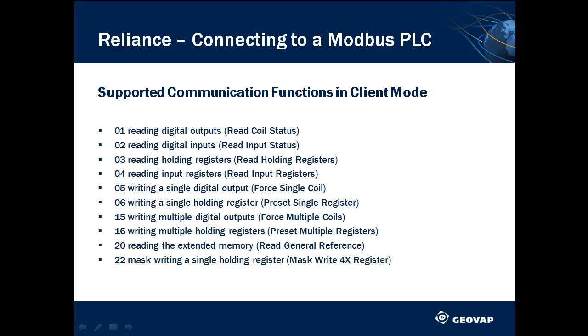Here is a list of all supported communication functions of the Modbus protocol in the client mode. What is important is that the functions can be enabled or disabled for each device. For example, if you want to connect a device that does not support function 15 — writing multiple digital outputs — simply disable this function and enable function 05 instead, which writes a single digital output.